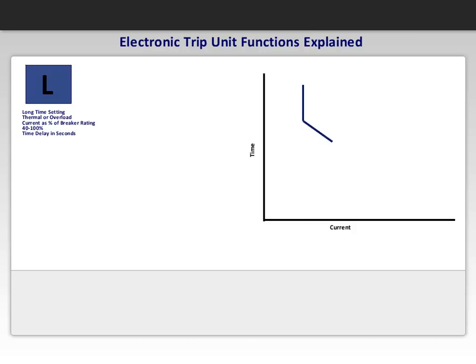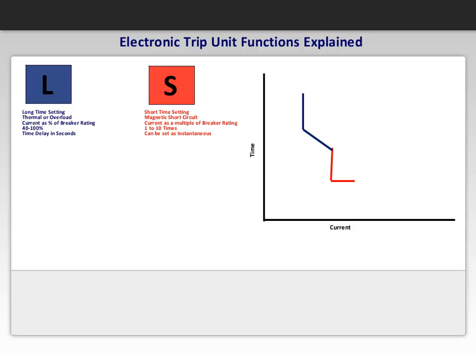The blue line here will demonstrate the adjustment available. The curve can be moved in and out along the current axis, as well as up and down on the time axis. Next is S, which stands for short time. This setting is associated with the magnetic or short circuit setting and is set as a multiple of the breaker rating, usually 1 to 10 times, and can be bypassed for just an instantaneous setting. It is represented by the red line on the curve. It too can be moved in and out along the current axis and up and down along the time axis.